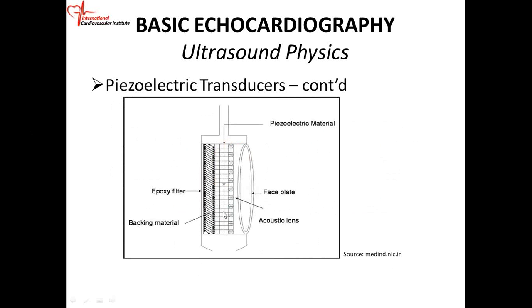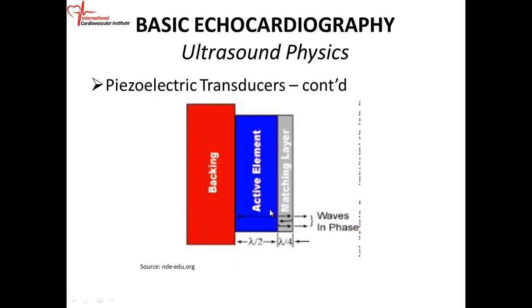So when you look at the transducer face on, the first layer you come in contact with is the faceplate. That's the first layer: the faceplate, the acoustic lens, the piezoelectric material, the backing material, and then the epoxy filter. So this is when you're looking at it face on: the faceplate first, the acoustic lens, the piezoelectric material, and then the backing material. All right.